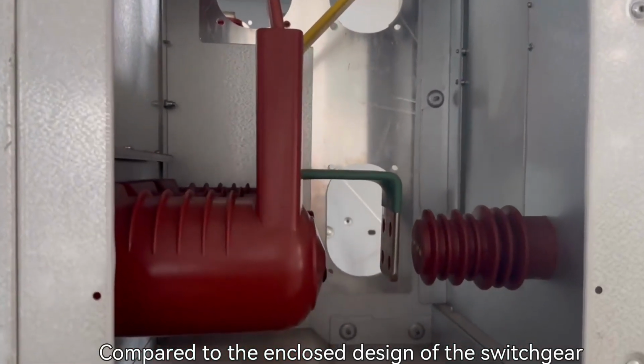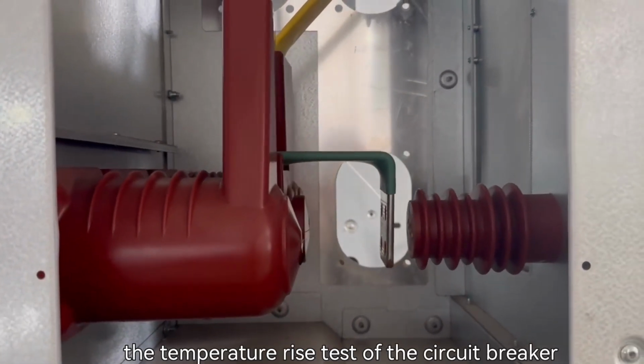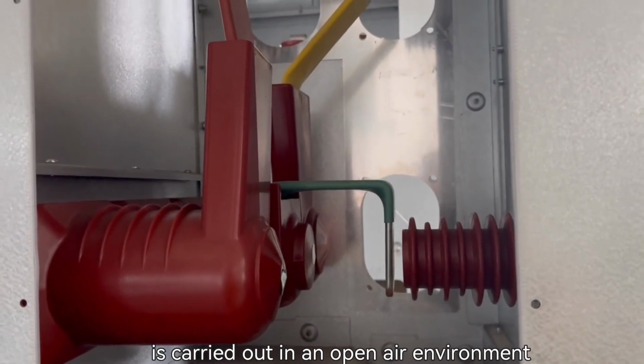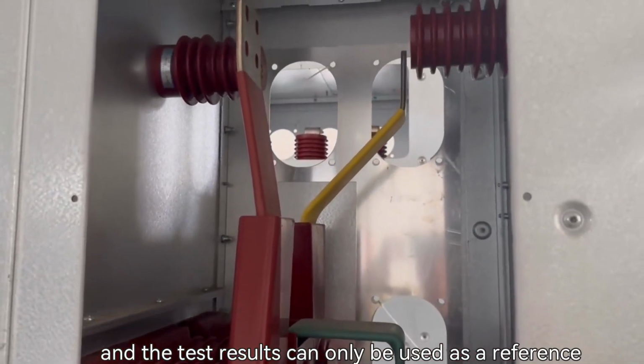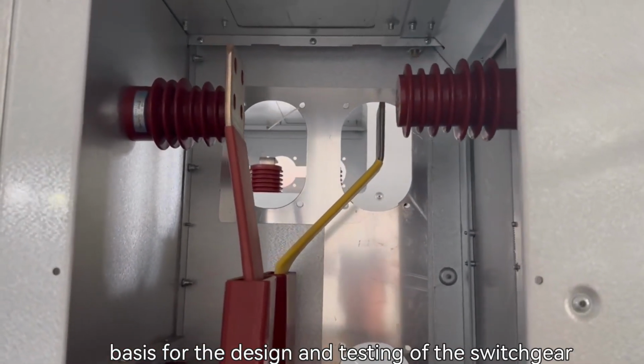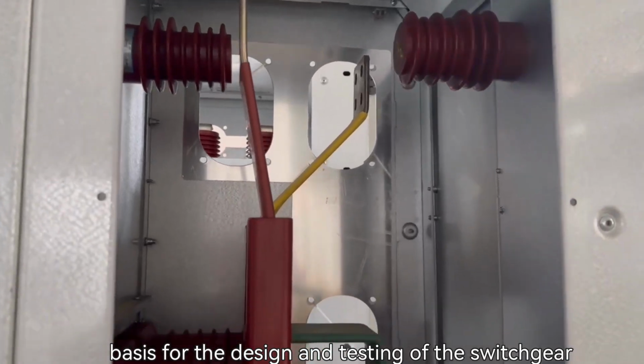Compared to the enclosed design of the switchgear cabinet, the temperature rise test of the circuit breaker is carried out in an open-air environment, and the test results can only be used as a reference basis for the design and testing of the switchgear cabinet.